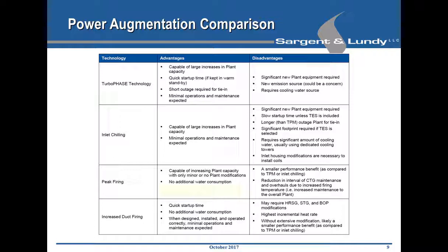In regard to the increased duct firing, which obviously is only available once you have an HRSG in combined cycle operation, you have the advantage of the quick startup time, but again, if the HRSG is not designed for duct firing from the very beginning of the design of the power station, it's quite difficult to implement. It requires substantial modifications to some of the equipment, and also the heat rate, the efficiency, is impacted by duct firing quite negatively. And therefore, in this overall comparison, we believe that Turbophase technology rates quite well, has a lot of advantages and very few disadvantages if you compare it with some of the other technologies that are available.